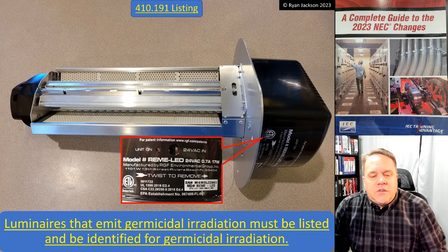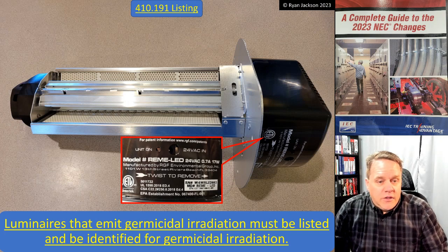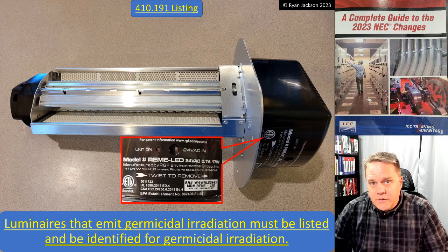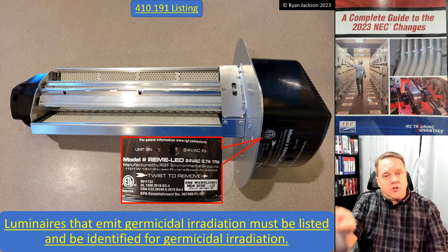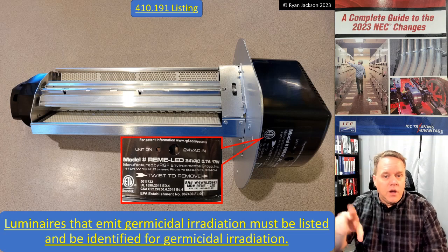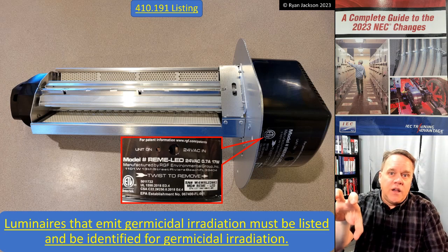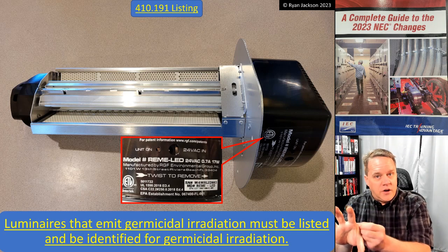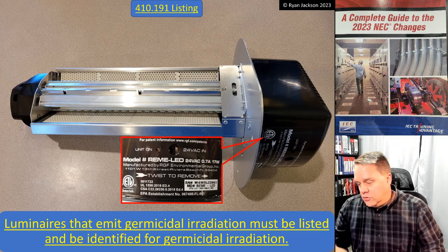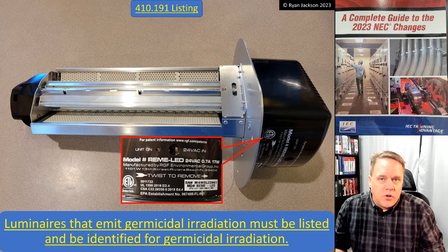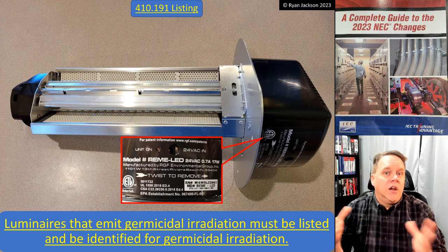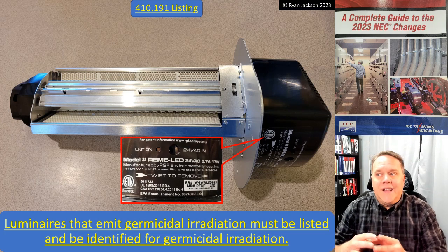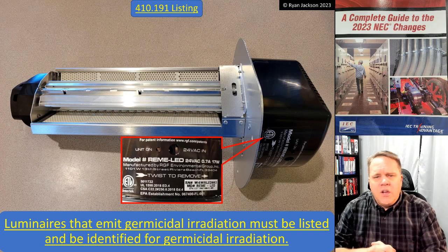Section 410.197 covers germicidal irradiation systems. I actually have one installed in my house — it goes right into the furnace plenum. The installation involves cutting a three-inch hole into the ductwork with a hole saw, inserting the luminaire into the duct, wiring it externally, and leaving it on. It uses ultraviolet lighting inside your air distribution system to kill germs.